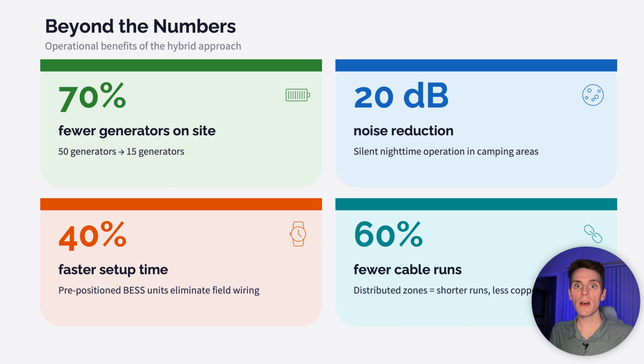Beyond economics, the hybrid approach reduces generator count by 70%, from 50 down to 15. It cuts noise in camping areas by 20 decibels, enabling silent nighttime operation. Setup time drops by 40% through pre-positioned BESS units, and 60% fewer cable runs means less copper and faster deployments.